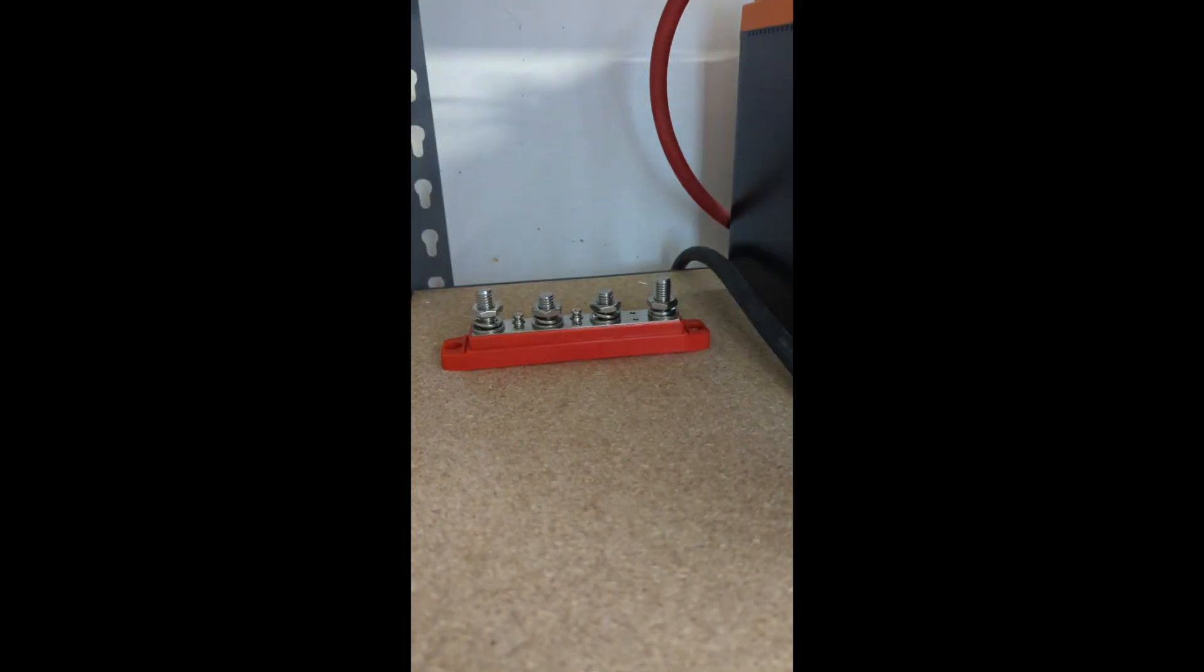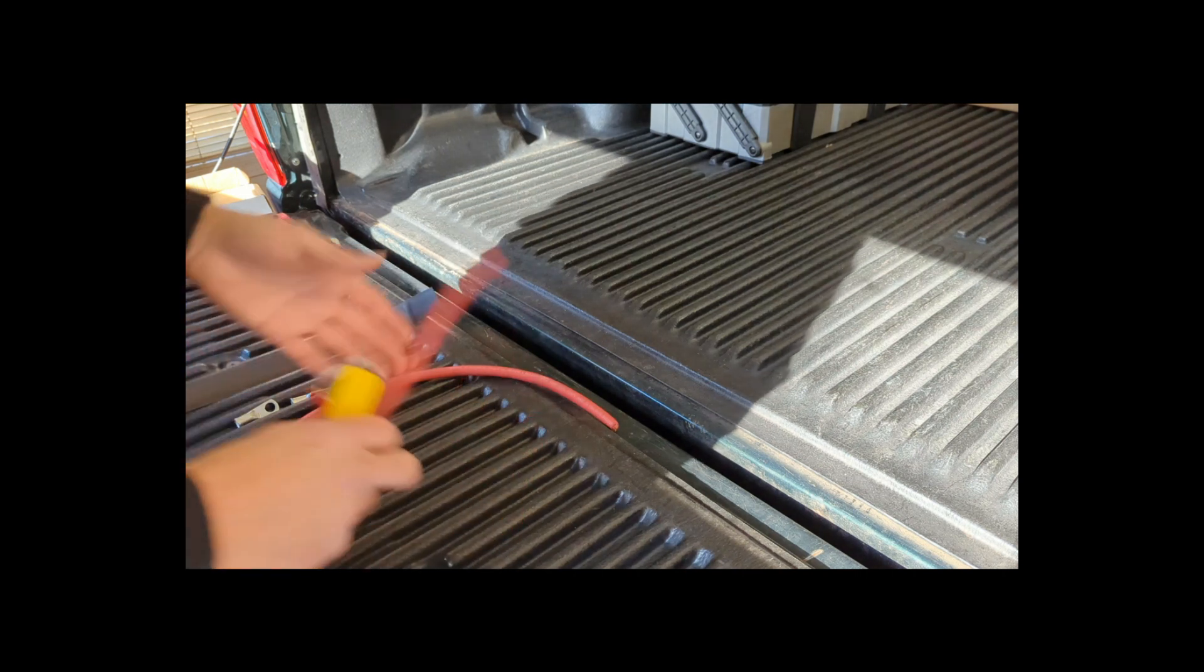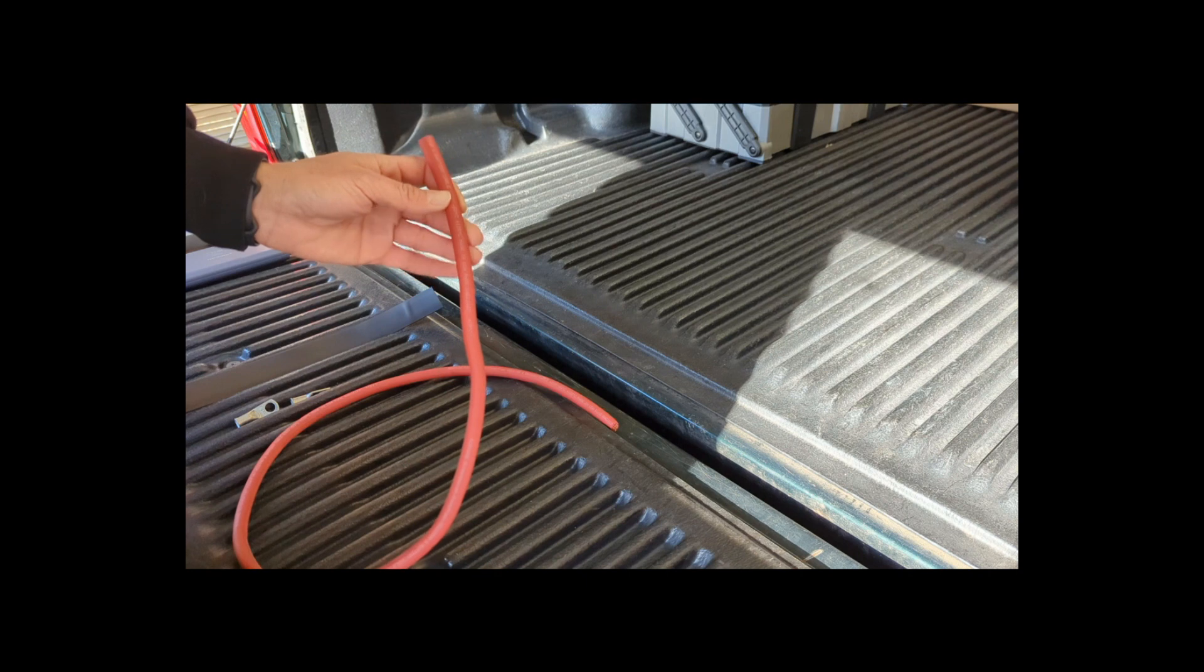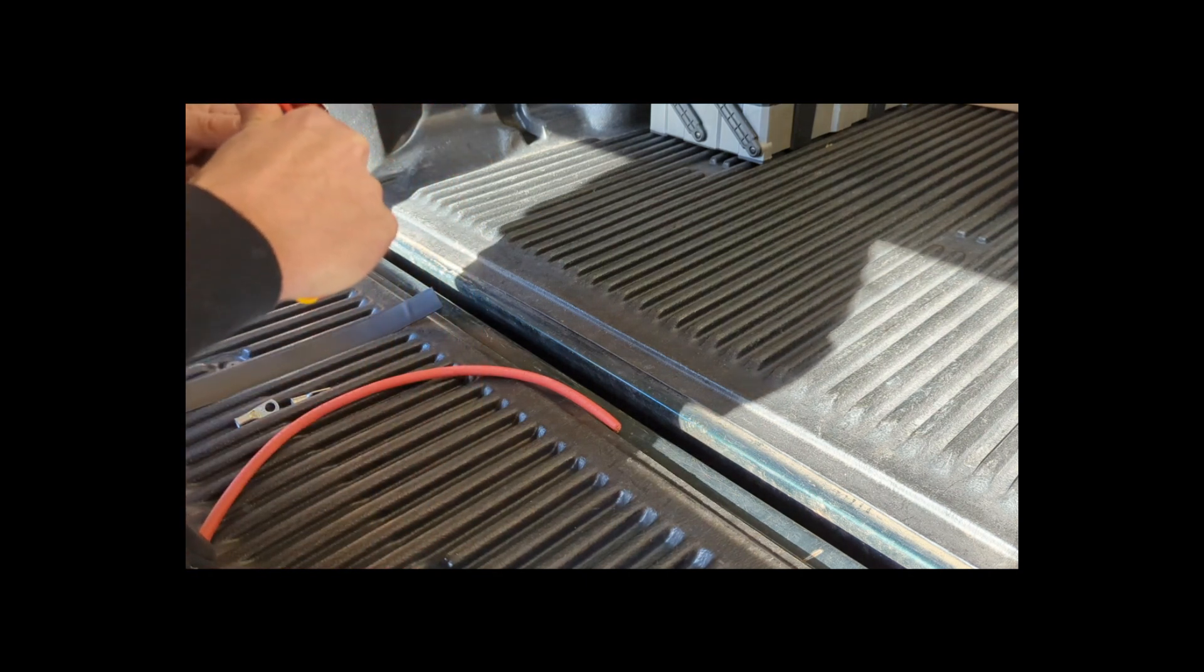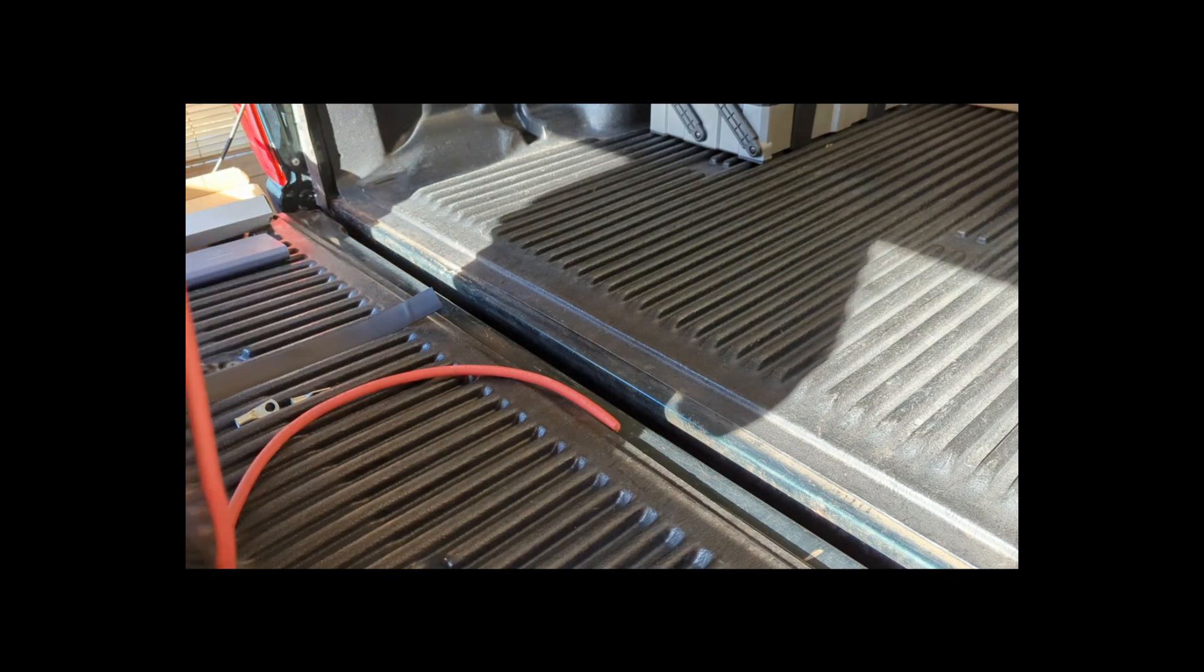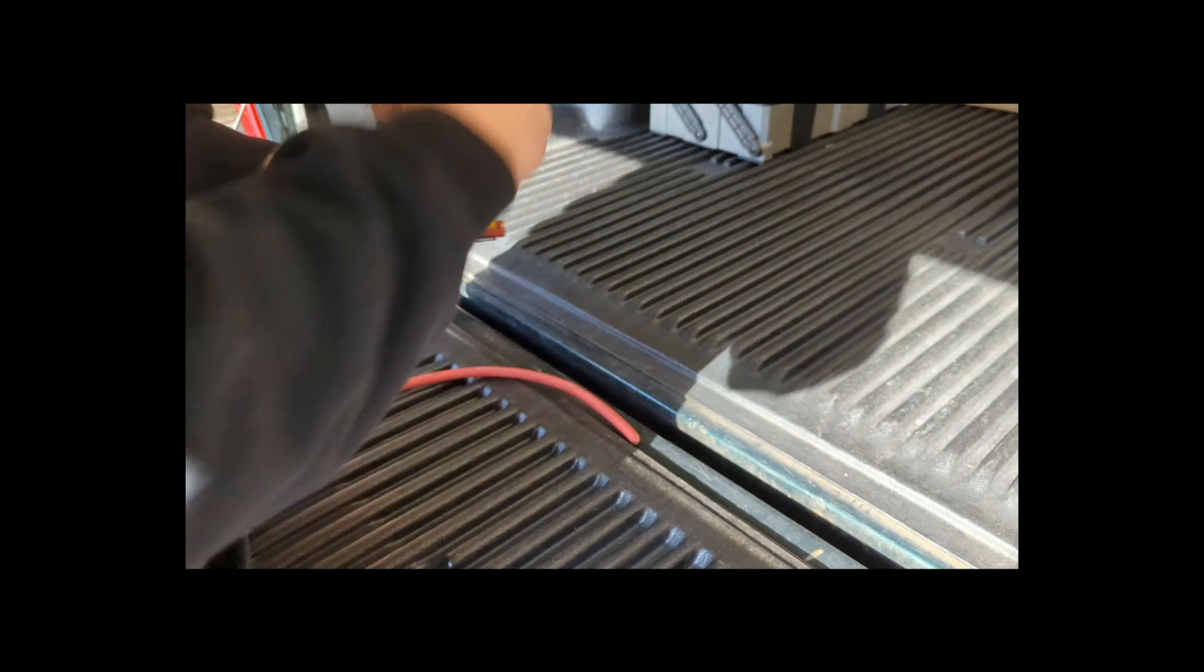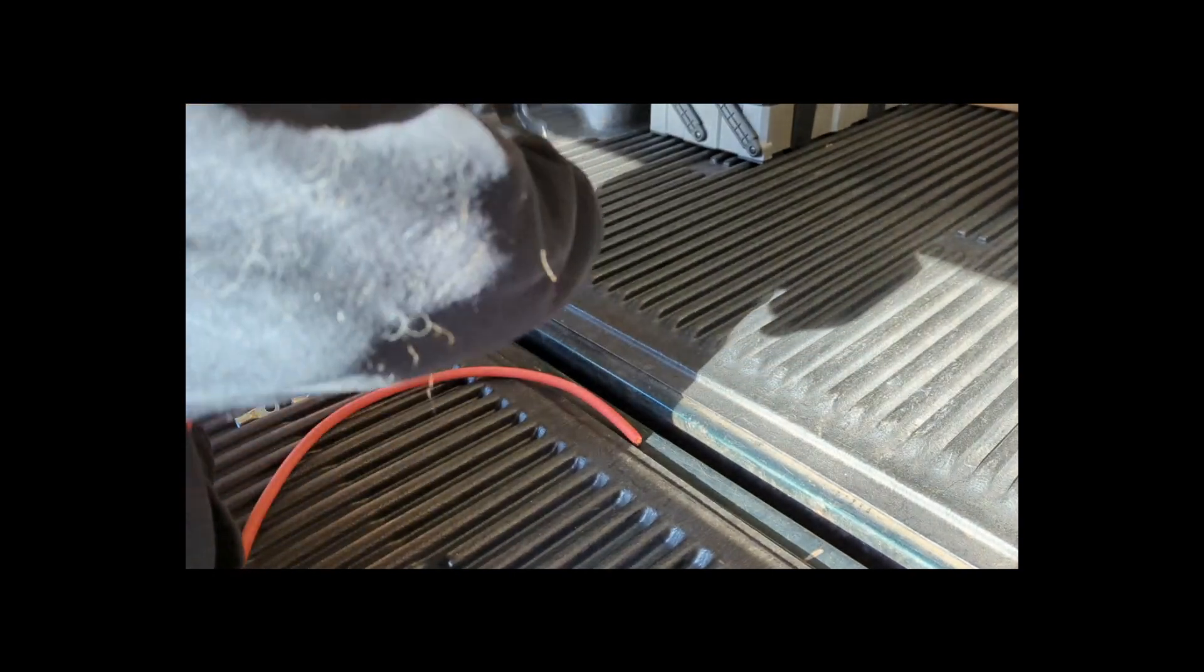With the positive bus bar mounted down, we can now run our positive connections coming from the charge controller and then going to the batteries. Before we can start attaching our wires to the positive bus bar, we need to make a new wire. This is a 2-gauge wire. It's going to be running from one of the batteries to the bus bar. We're going to strip it down and install lugs on it.